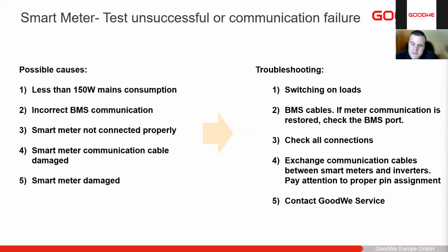But it's very, very seldom that the smart meter is faulty. Normally, if they are faulty, they don't work at all. If they are on and they give readings and everything, normally there's no problem with the smart meter itself. It's normally a wiring issue that needs to be fixed.